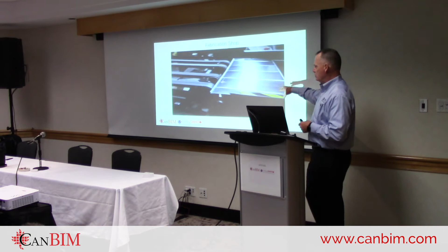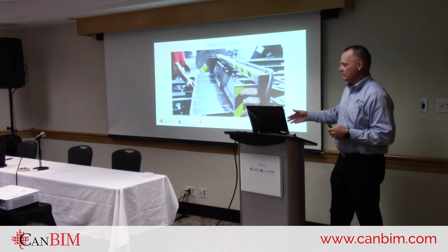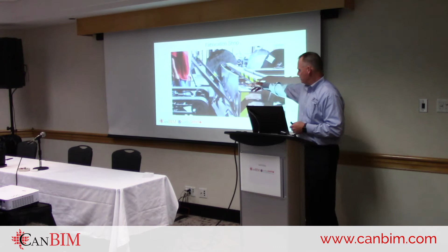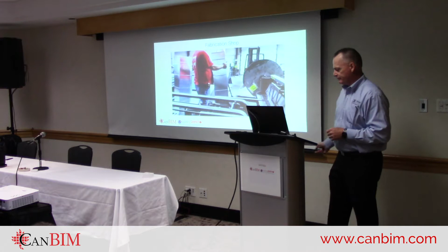When we're doing modeling, we want to make sure we use as many full joints as possible, since full joints save money. For example, if this is a 60-inch coil with an S and drive connection, that's going to be a 59-inch piece of ductwork. But if it's 58 and 3/4 inches, that's a fitting, and that fitting has to go a whole separate route through the tables - it costs so much more. The linear feet of work built per day off this coil line compared to a fitting is unbelievable. So when modeling, we want to eliminate fittings and use as much straight duct as possible.